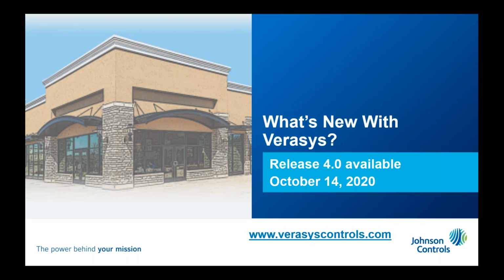And then as part of our field trial period, we had sites that included both Carrier and Trane RTUs. From a Verasys perspective, they come in just like any other device. They typically have between 200 to 300 unique objects, which is a lot. So it was certainly a learning curve on our part to figure out what each and every one of them meant and how they work. But yes, we certainly did test those out thoroughly.